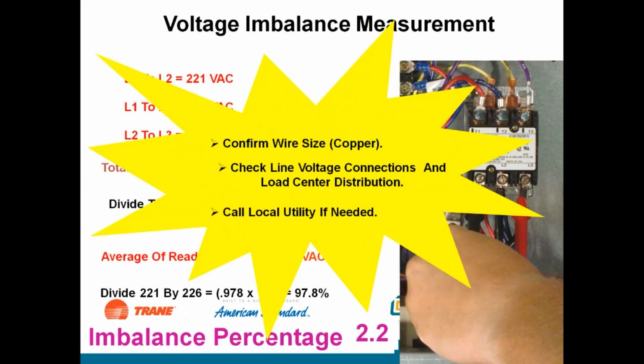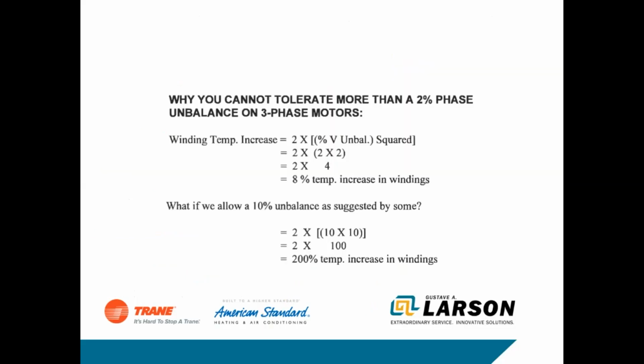If you have a voltage imbalance, the first thing, of course, is make sure you've got the proper wire size. Second, check the line voltage connections and load center distribution. Make sure we don't have any loose connections, bad breaker, any of that kind of thing. And if that looks good, the best thing you can do then is call an electrician or get your local utility involved, because somebody's got to balance the load, and balancing a load is not that simple to do. You've got to start moving breakers and doing different things in the panel. So identify the problem, and if you don't see the simple fixes, get an electrician on board or the utilities if necessary. But it's so important for this reason.